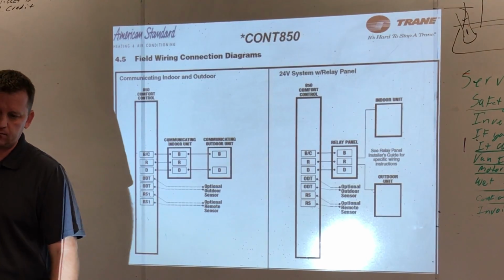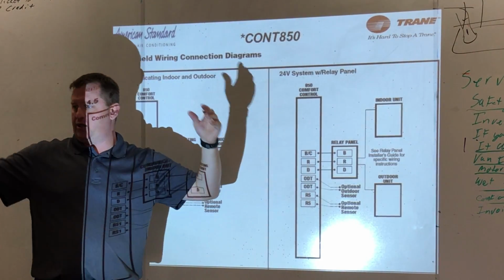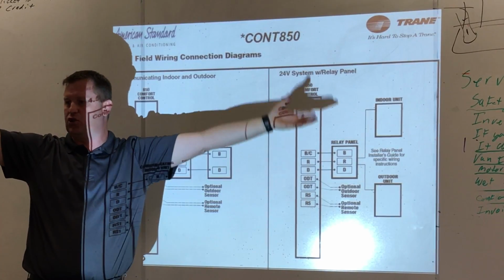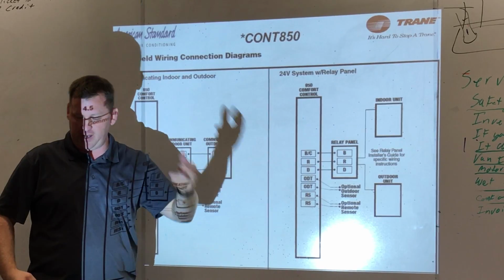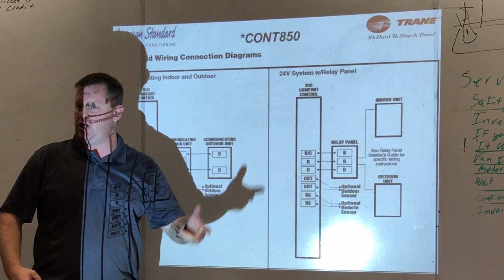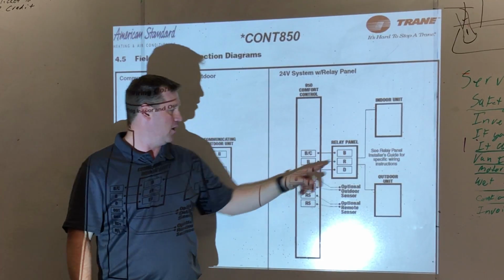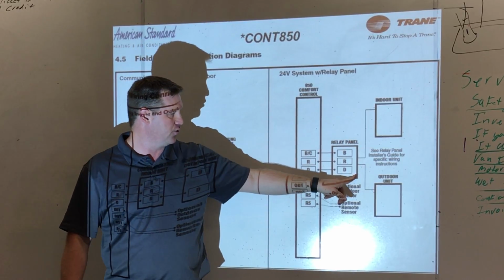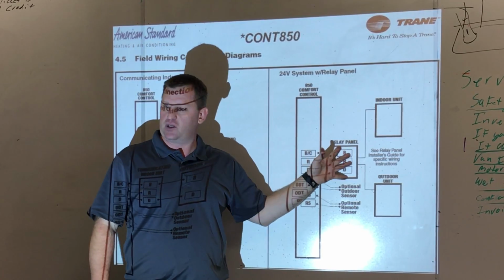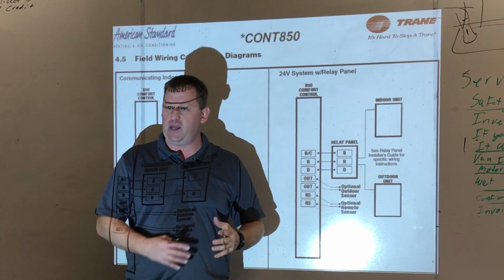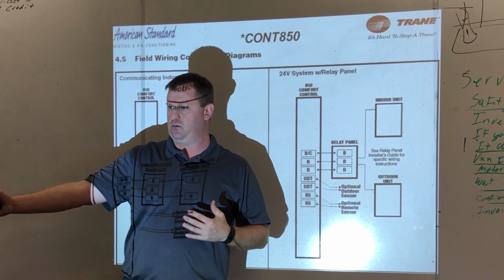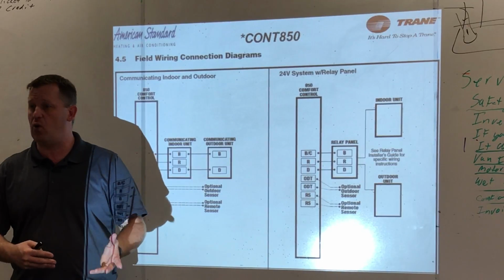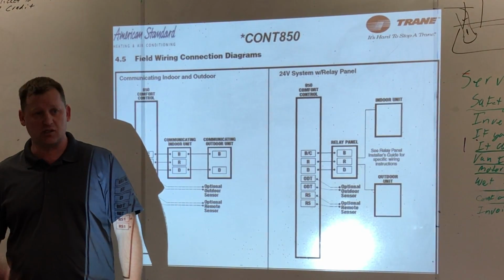Okay. Alright, so I told you we had to have 12 wires, plus the 2 for the outdoor sensor, right? Because we had TAM7 with a 2-stage heat pump and a humidifier. Well, now if we use the relay panel, we've got RDMB to RDMB on the relay panel, outdoor sensor ties to the relay panel, indoor and outdoor unit ties to relay panel. Now you don't have to repull the stat wire. Okay, because in some cases repulling a stat wire is a 2-hour, 3-hour process for 2 guys, right?